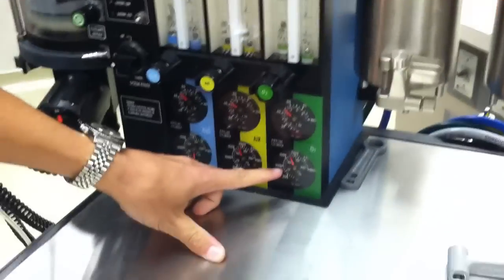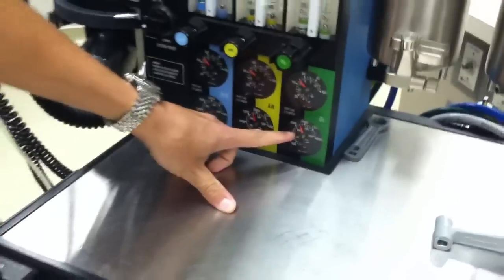I'm going to plug in my oxygen. And when you watch me push the O2 flush valve this time, that pressure will never go down. That's why we disconnect our pipeline pressures.